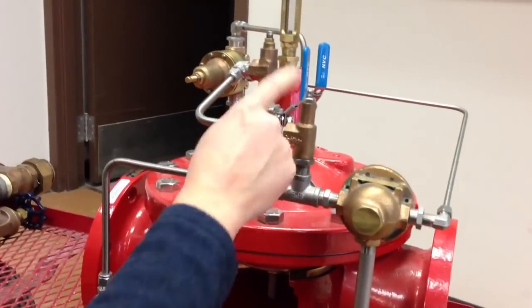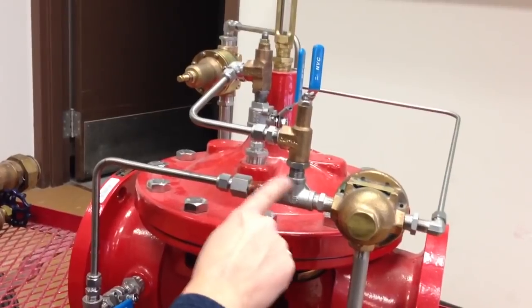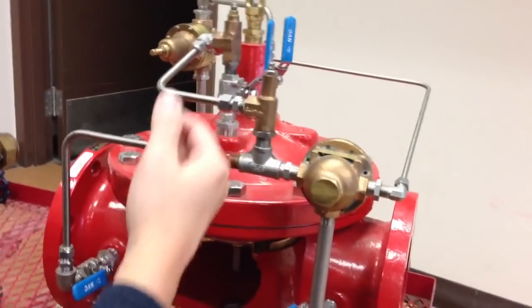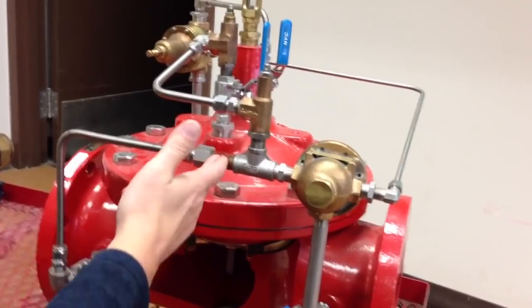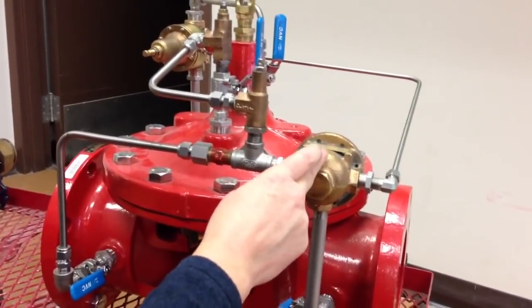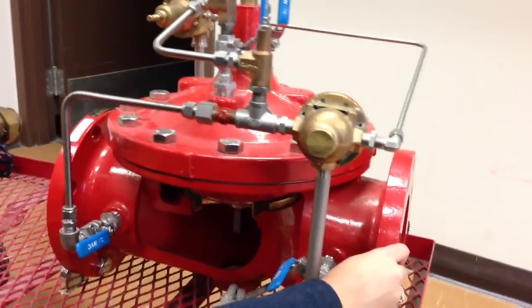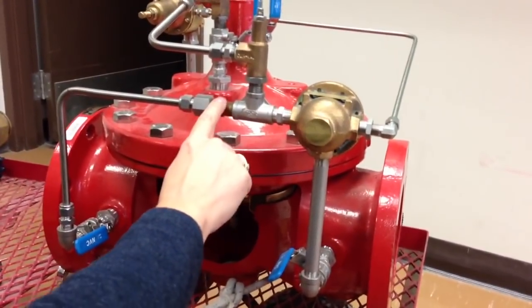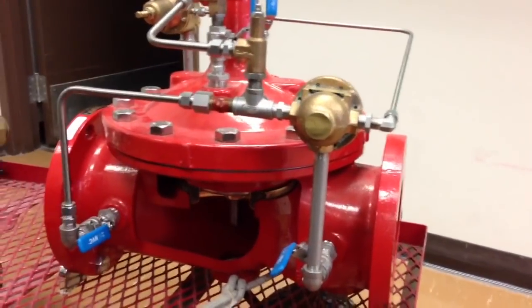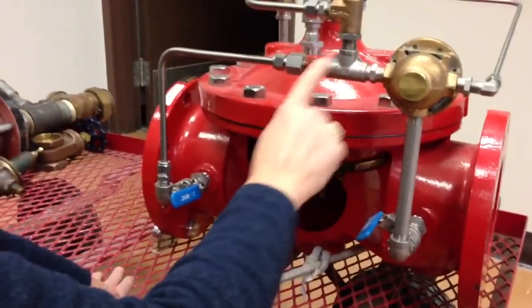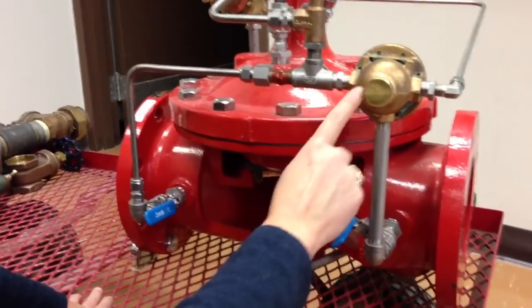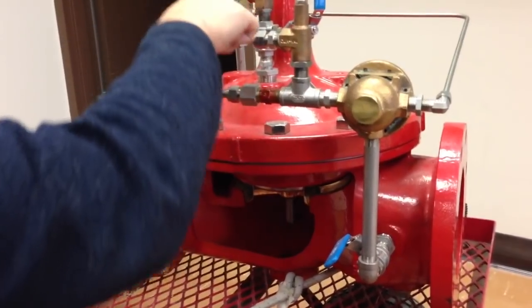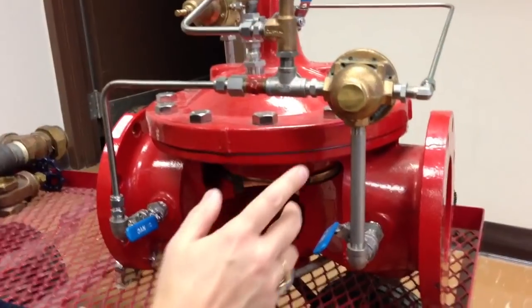And there's your Dole valve, which just controls how much water gets into the system to start with. You need that, and it's always a constant amount coming through here. Whatever it happens to be, 0.1 liters per minute, that's what you get coming in here. This one opens and closes based on what's happening on our downstream pressure side. So if this is closed, all of the 0.1 liter per minute which this is letting in is going to get forced onto the top of the valve. If this is open all the way, then this one is going to allow that 0.1 liters per minute to come off here. But if it's full open, it's going to be looking for more water, so it's going to start pulling water from here and opening the valve. Make sense?